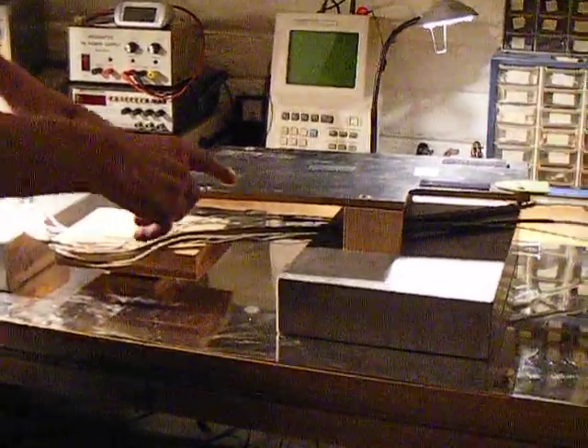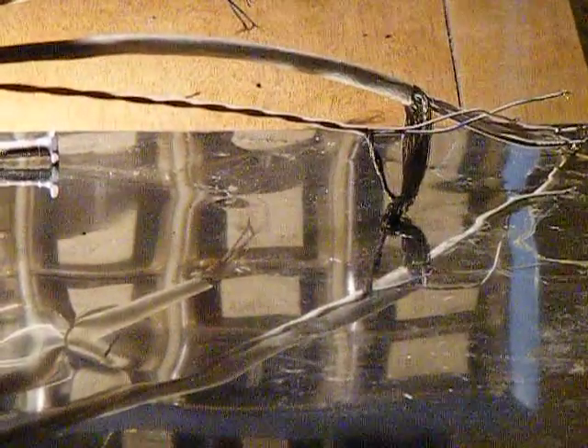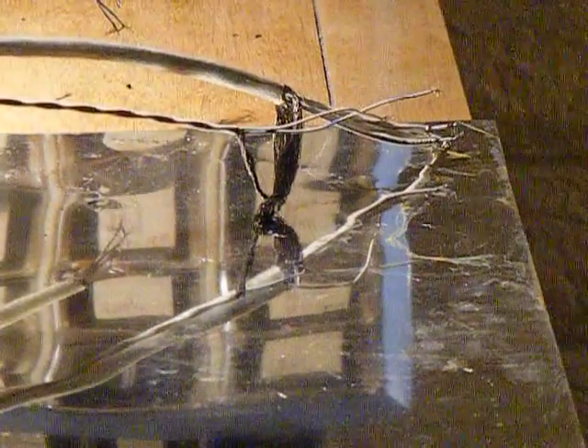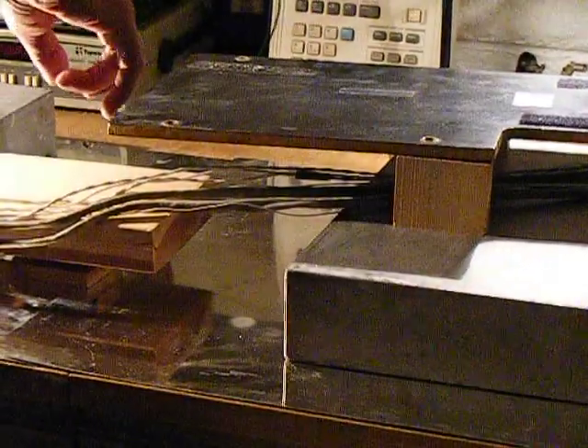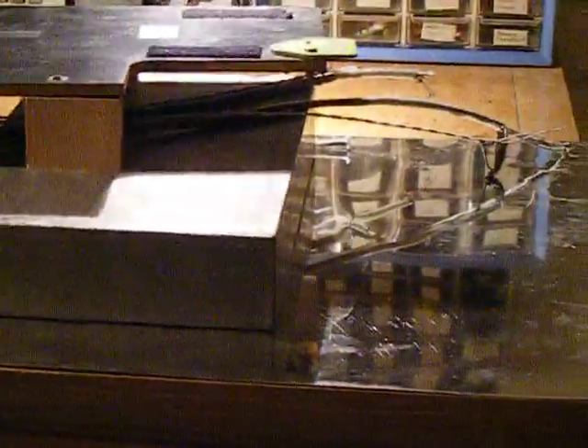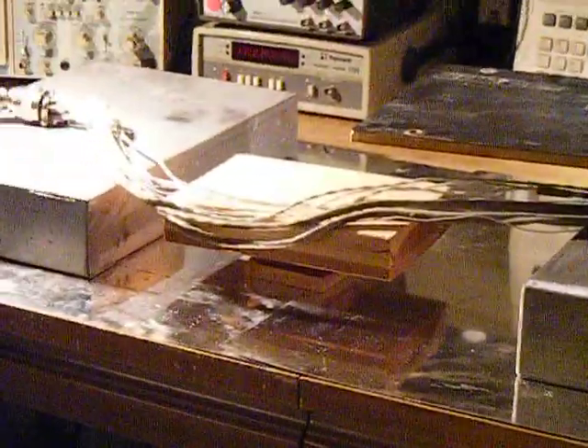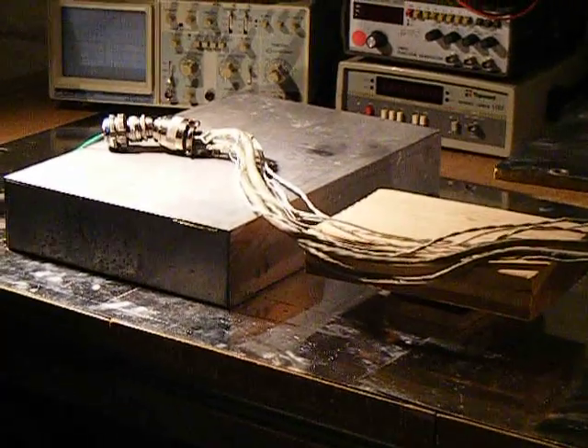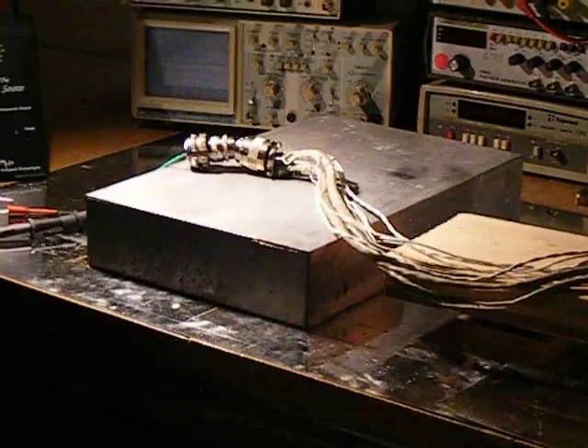The aviation grade wiring is all shielded. We've tied the shields together and connected them, contacted them with our chassis ground, as would be found at the other end of the cable. In one of these wires, we have shorted the core wire to its mesh shield. We're going to first determine which wire is shorted, and then we're going to find where the short is.